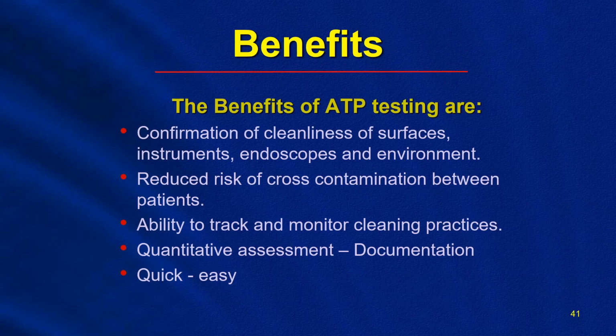So some of the benefits of ATP testing, again, it's a confirmation of the cleanliness of surfaces, of instruments, endoscopes, and even the environment. These devices can be used to test surgical environments in the operating room, overhead lights, OR tables, patient waiting areas, procedural rooms. It will reduce the risk of cross-contamination between patients because you will be able to determine if items are truly, truly clean. It has the ability to track and monitor cleaning practices.